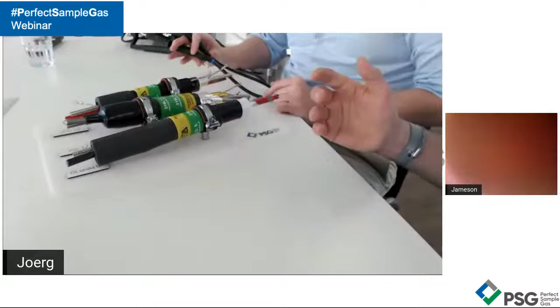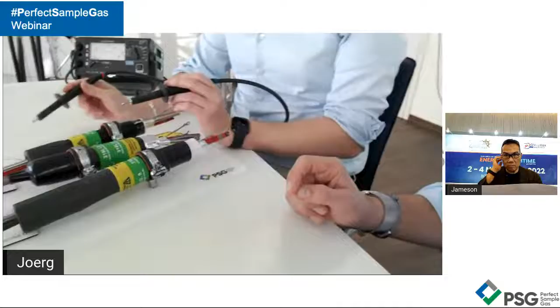If this type of heated sample line is grounded everywhere, there's no issue, no problem. But remembering the installation we just saw in the analyzer container, it's very hard to ensure that it's grounded to the cable tray everywhere - and we mean really everywhere. There shouldn't be more than about 2 square centimeters without protective earth underneath it. So it's much easier to achieve this conductivity with one of our conductive outer jackets.